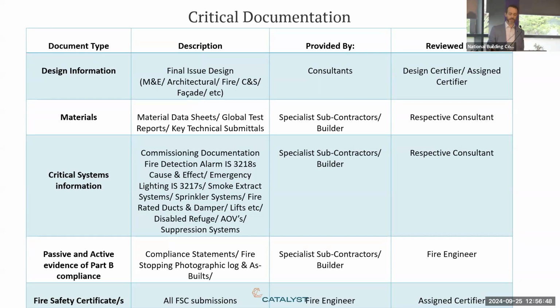As-built information - that's a key one now, because things move. If you go by the final issue design and it hasn't been updated to an as-built design, they won't be able to find the equipment they're meant to maintain. This should be getting validated by the M&E consultants to make sure it's actually accurate. I know they don't necessarily agree with me on that, but I do think it should be insisted upon that the as-builts are accurate, or at least sanity checked.